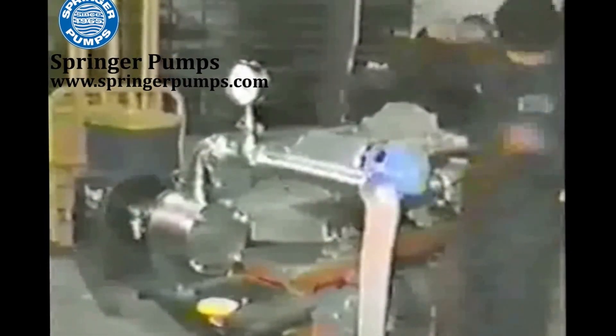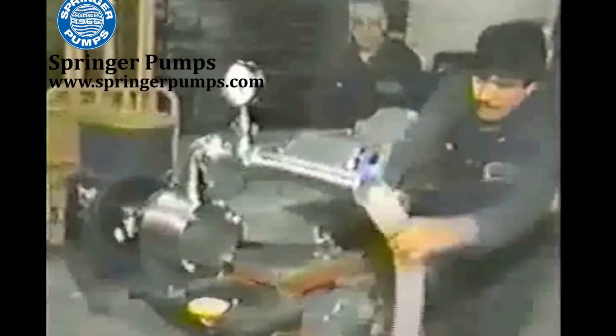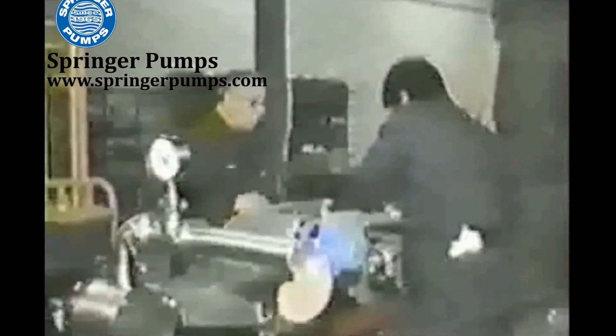The amperage pull on the motor was right at about 4.8 amps, three-phase 230 volt, which equates to about 1.2 to 1.3 horsepower — a very small amount of horsepower for this viscosity product. Amazing. But Dan wasn't quite through with the day's testing. In the following sequence, we see another difficult product combining...